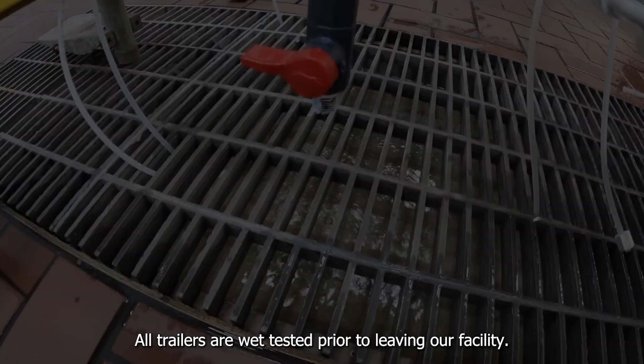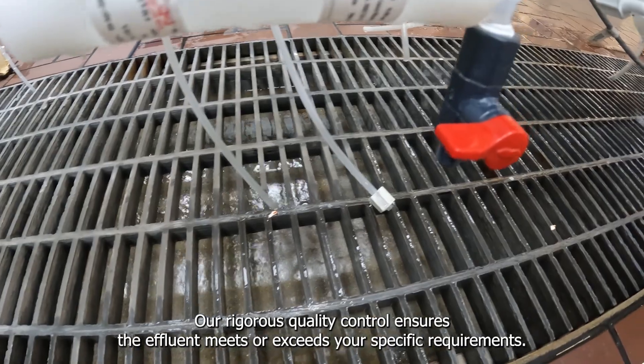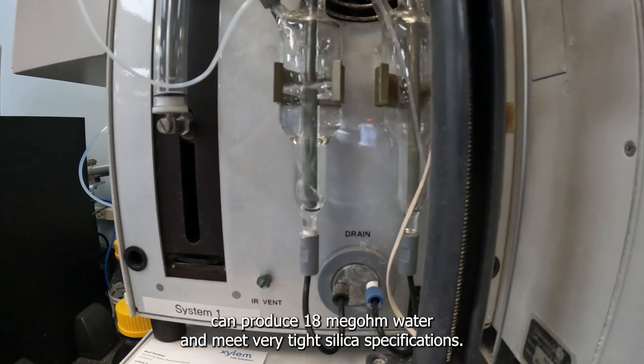All trailers are wet-tested prior to leaving our facility. Our rigorous quality control ensures the effluent meets or exceeds your specific requirements. Trailers leaving our facility with freshly regenerated resin can produce 18 megohm water and meet very tight silica specifications.